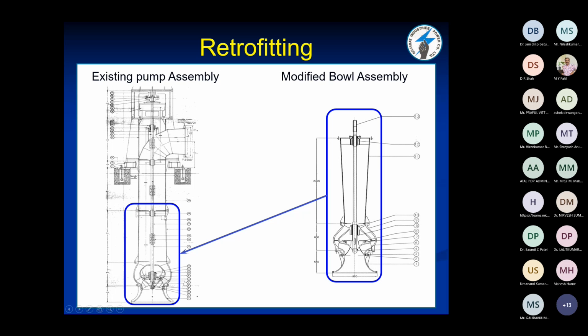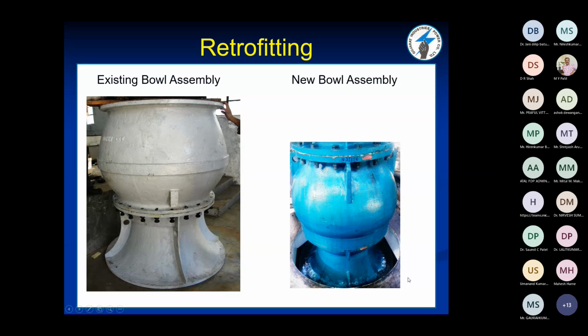Originally, this was the pump, the existing pump assembly, and now it is a pump with a modified bowl assembly, a lower capacity pump. We have reduced the size of the pump. This pump is also of lower capacity, and the motor and all the system will remain the same. Only this bowl assembly will be changed. This is the existing bowl assembly, and this is the new bowl assembly of lower capacity. Dimension wise it is smaller, and capacity wise it is also smaller.